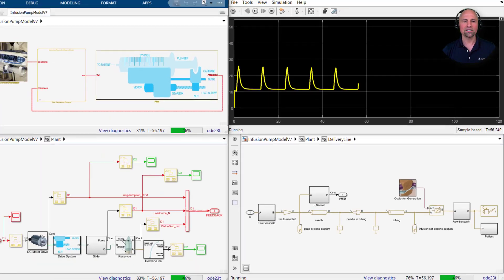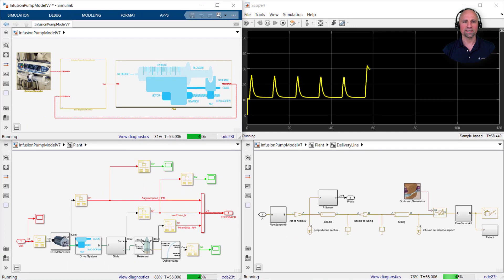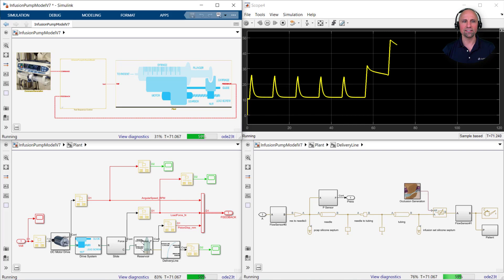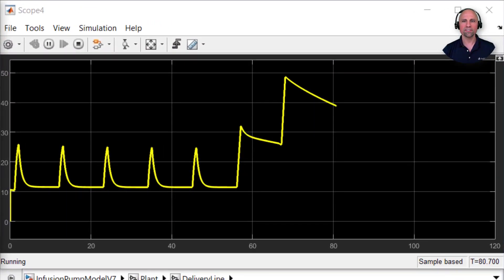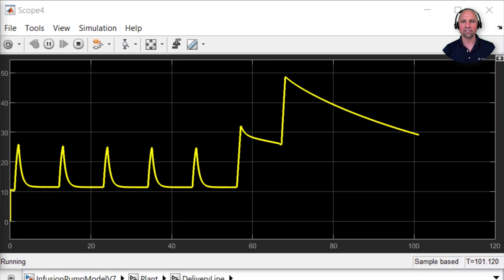One of the advantages of creating a full system simulation is we can easily and safely inject faults into the system to test that the device and software behave as required. Here we've introduced an occlusion into the delivery line just before the one minute mark. As designed, the system detects the resulting resistance and commands the motor to stop applying a force to the plunger.